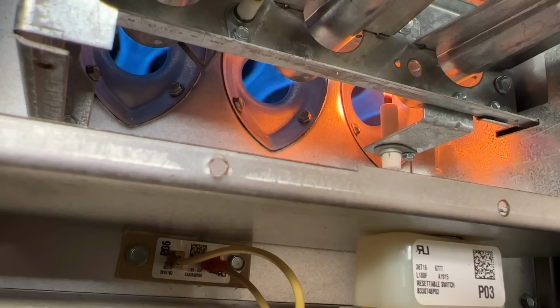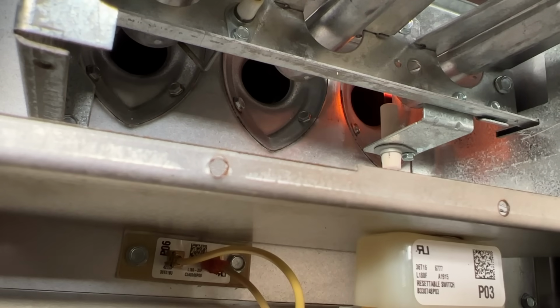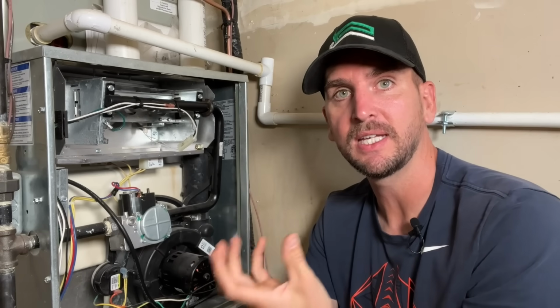burners start, but then after 2 or 3 seconds, burners will stop. So they will not continuously stay lit, and then your furnace can cycle through the same state. So we're getting to step 4, but we're not getting to step 5 or step 6.